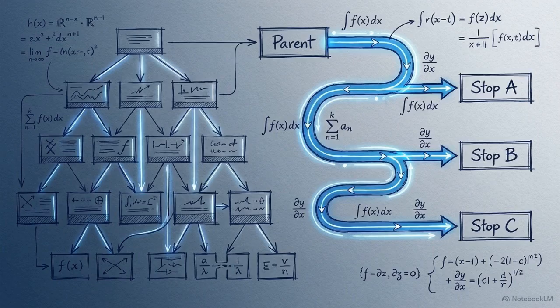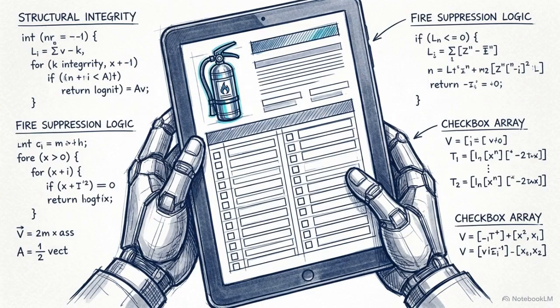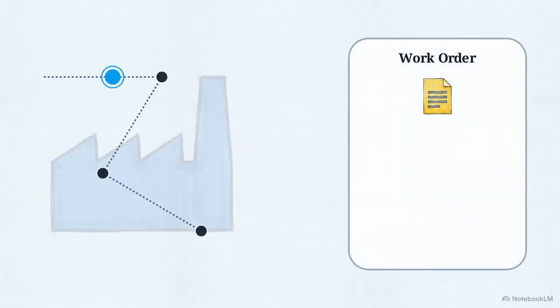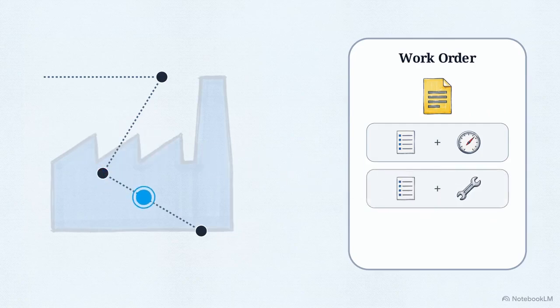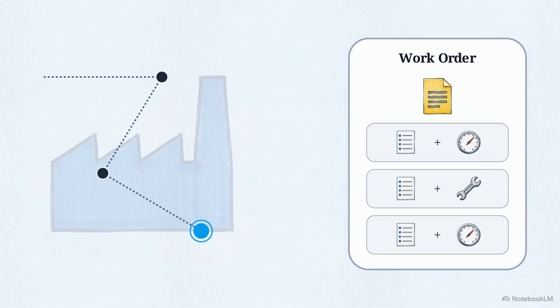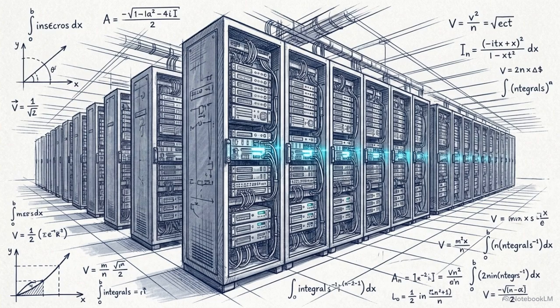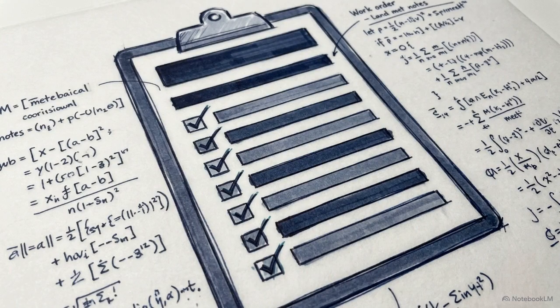Routes, shown on the right, operate differently. They are designed for linear, multi-stop inspection paths across a physical space, rather than structural shutdowns. A fire extinguisher inspection route utilizes a single parent work order. As the technician walks the route, the system populates that single work order with individual child tasks for every physical stop on the path, each with its own asset-specific meter and job plan. Hierarchies blast simultaneous work across deeply integrated complex systems, while routes streamline high-volume, repetitive field checks into single executable checklists.